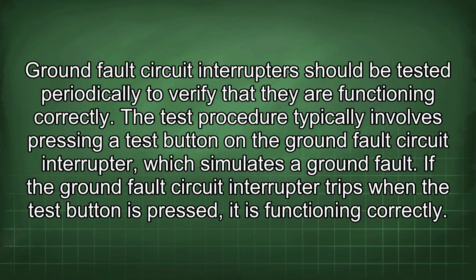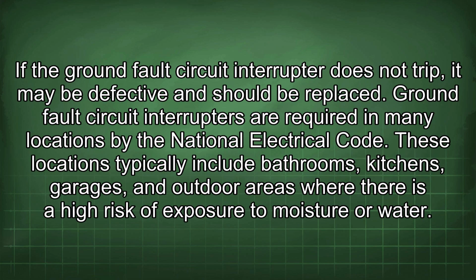Ground fault circuit interrupters should be tested periodically to verify that they are functioning correctly. The test procedure typically involves pressing a test button on the ground fault circuit interrupter, which simulates a ground fault. If the ground fault circuit interrupter trips when the test button is pressed, it is functioning correctly. If the ground fault circuit interrupter does not trip, it may be defective and should be replaced.